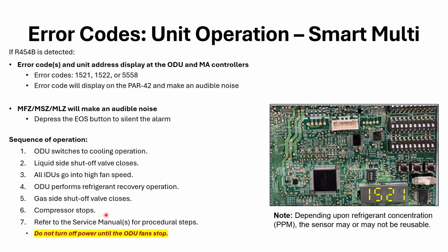Compressor stops, and then at that point we can power the system off. It talks about going to the service manual for the process if you need to read up on it. Let's see if I have any more notes on that. Let's see, normal pump down operation is prohibited in the event of a refrigerant leak because there is no low pressure sensor and the refrigerant leak point could cause air into the system.